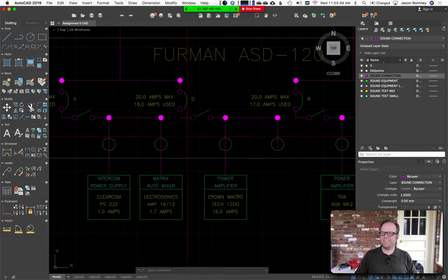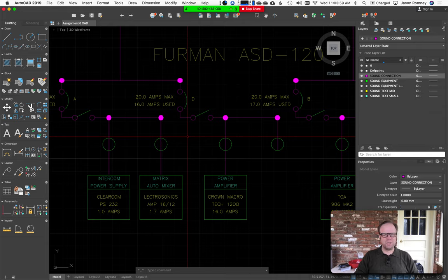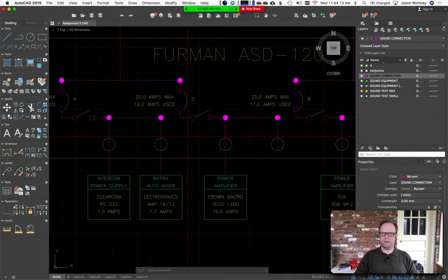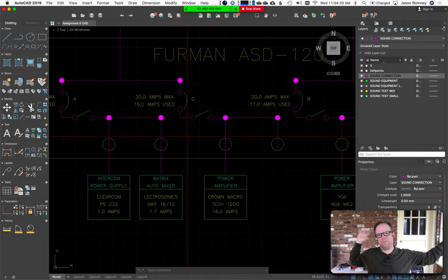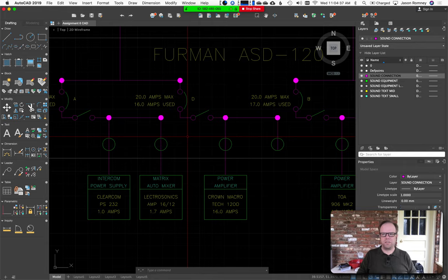So you really don't want to be in that situation. One of the things the power diagram can help you with: if you know where everything gets powered from, and you realize your amp rack went down but your mixing console is still on, you can look at your power diagram and say, which breaker feeds the amp rack? You can go check if that breaker is tripped. First, just try to turn the breaker back on. If it trips again, you start turning off some non-essential amplifiers — maybe surround sound effects amps — and try to reset the breaker to get through the show.